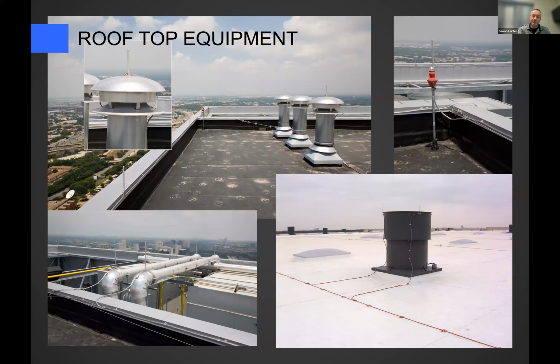Here are pictures of protecting rooftop equipment. Like I said, you do have to put lightning rods on top of rooftop equipment that extends up outside the zone of protection. You can imagine if you were rolling that 45-meter sphere up and over this building, it's going to hit the edge, then it's going to hit the aircraft warning light, then it's going to hit those mushroom vents there, or those air handling vents. So that's why we want to put lightning protection on top of those.